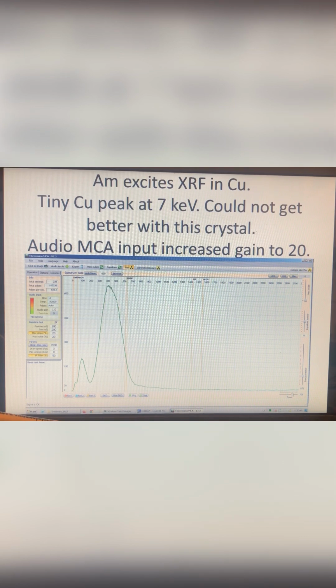Then I also tried X-ray fluorescence, and it was not very successful. I put a copper plate between the americium source and detector, and a small peak appeared which should be around 7 keV, the characteristic line of copper. I could not get better results with this crystal. And to record such small energies, the MCA microphone input gain was increased to 20.